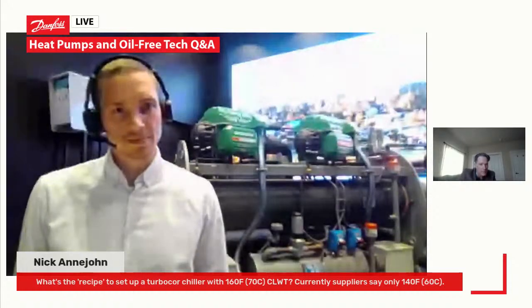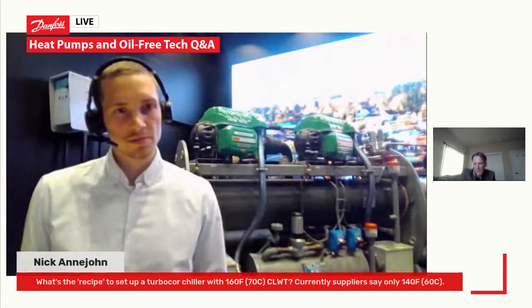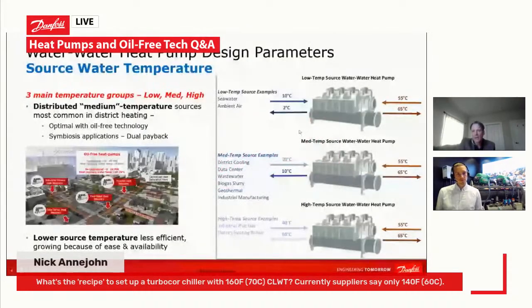So this is showing the source water temperatures and the variations. For a low source water temperature, such as seawater or ambient air applications, generally your combination of compressor, or the recipe to his question, that you'll use for the final heat pump solution is very different from what you'll use for a higher source water temperature application, such as industrial flue gas or a district heating return out distributed in a system. And then you have the medium source temperatures. So low source temperatures end up going back to the source at about 2 degrees Celsius, medium about 10 degrees Celsius, 30 for the high temp.